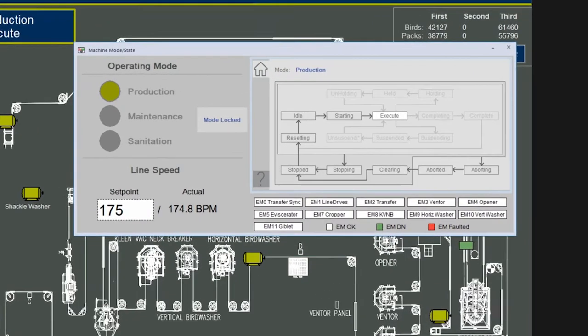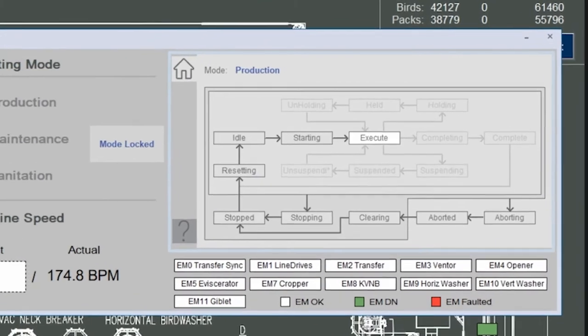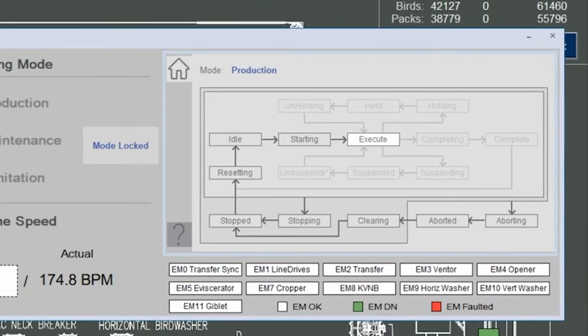TR88 is a classification for different states of the machines. The code is broken down into equipment modules that follow the state model. This is an industry standard method for knowing the state of the machine while also providing a standardized blueprint for code structure. Data is available via OPC UA connectivity.